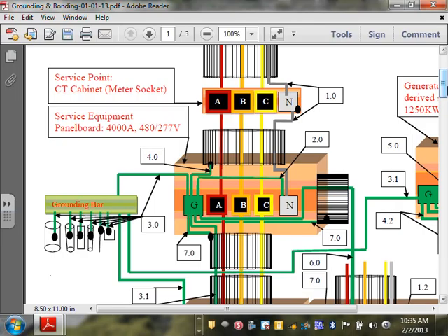Everybody understand the whole system? That's why in a dwelling we end up with what? 2, right? The water pipe coming into the building and a ground rod. If you don't have a water pipe, you have to drive 2 ground rods, or 1 ground rod and a plate. You have to have 2 sources. If it's a rod, it needs to be supplemented. We don't depend on a rod by itself. Okay, everybody understand the terminology with that? Okay, so let's go to number 4.